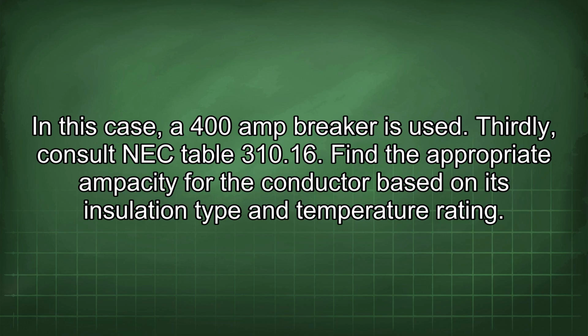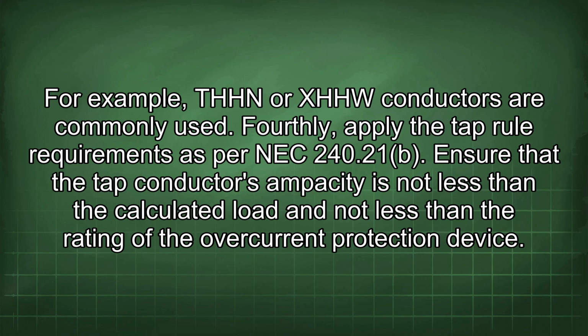Thirdly, consult NEC Table 310.16. Find the appropriate ampacity for the conductor based on its insulation type and temperature rating. For example, THHN or XHHW conductors are commonly used. Fourthly, apply the tap rule requirements as per NEC 240.21.